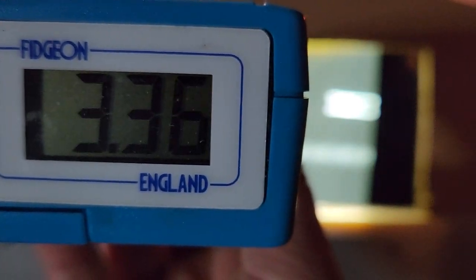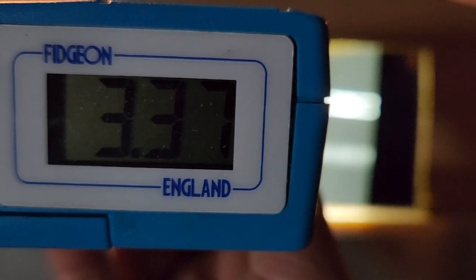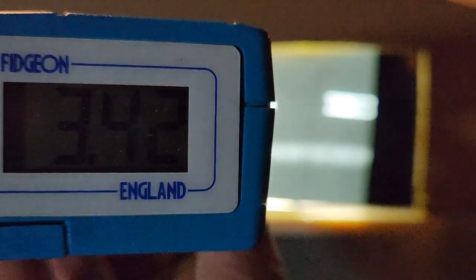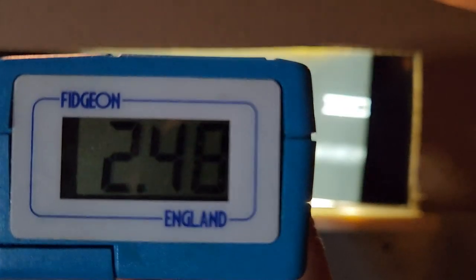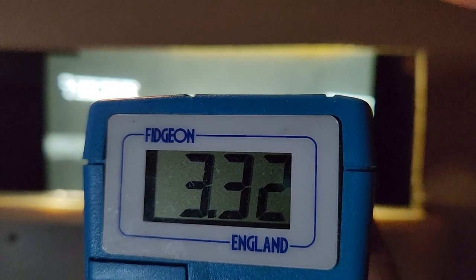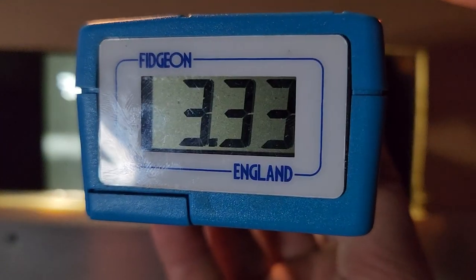But is that correct? Well, what we have to do first, I'm just going to lift my light guard up so I can get to where there's no image directly onto my light box. And then I can zero that off of there. Right, and I'll just drop this back down. So now, when I put it onto the image, I'll get my densitometer reading. So that's 3.37. And I can take them from a few different places. 3.42. We'll take one in the weld. 3.32. You know, bounce around a little bit. 3.3.